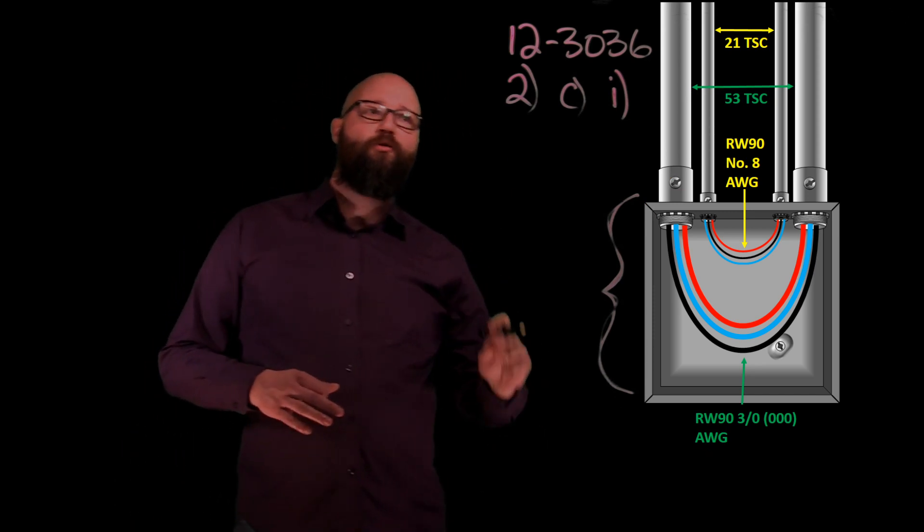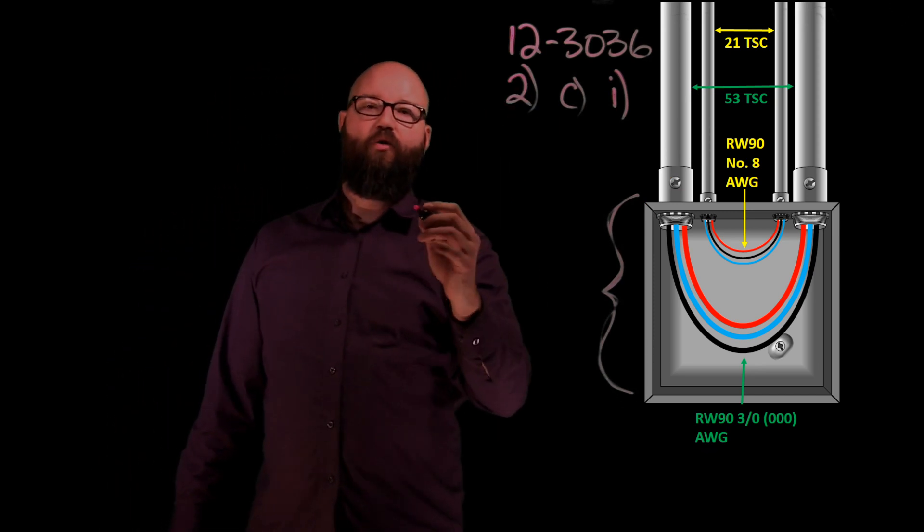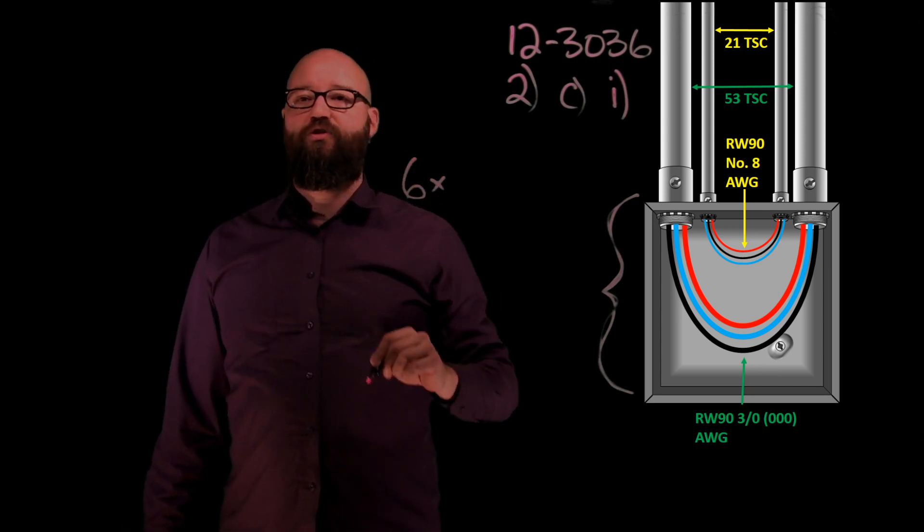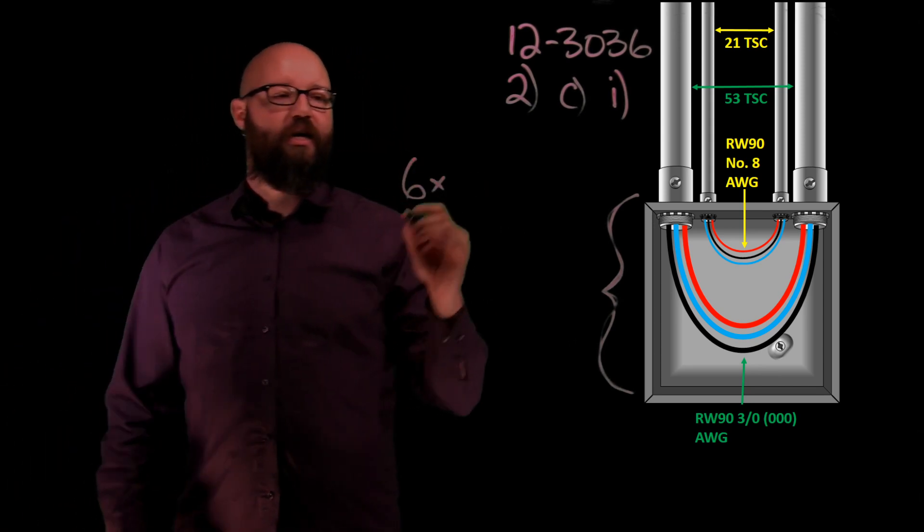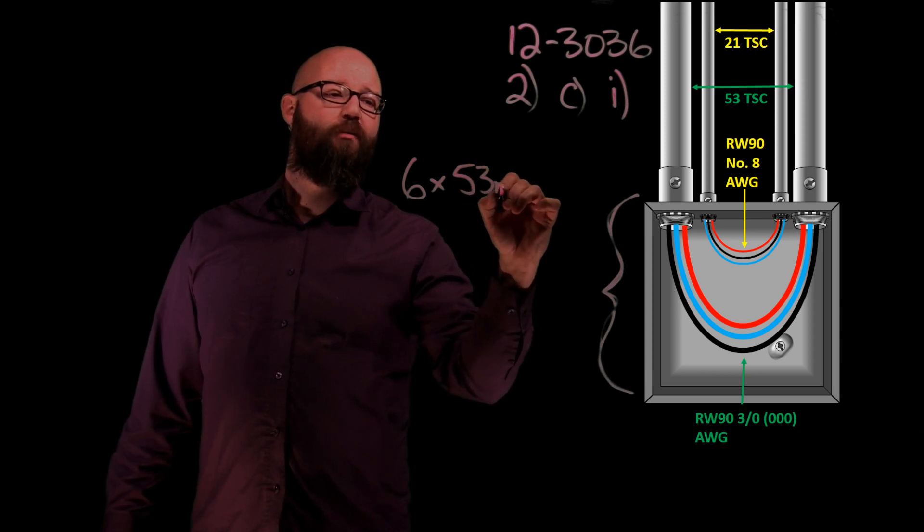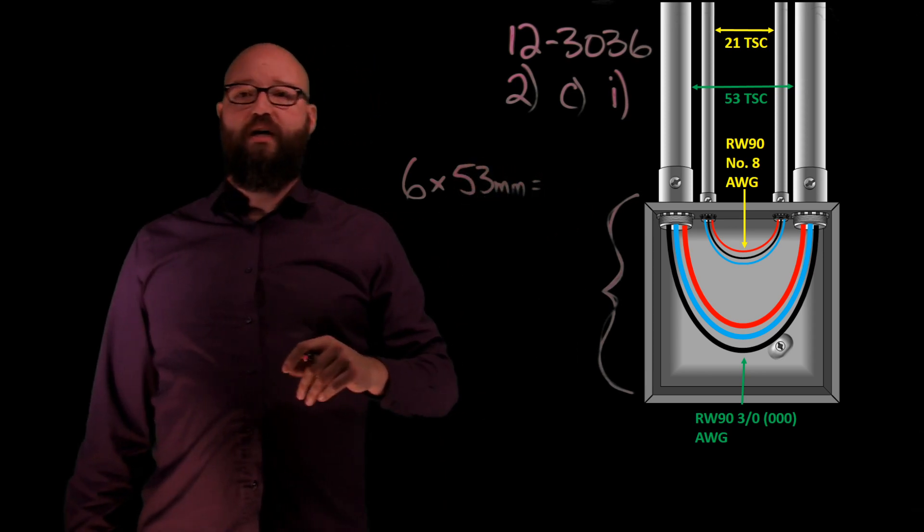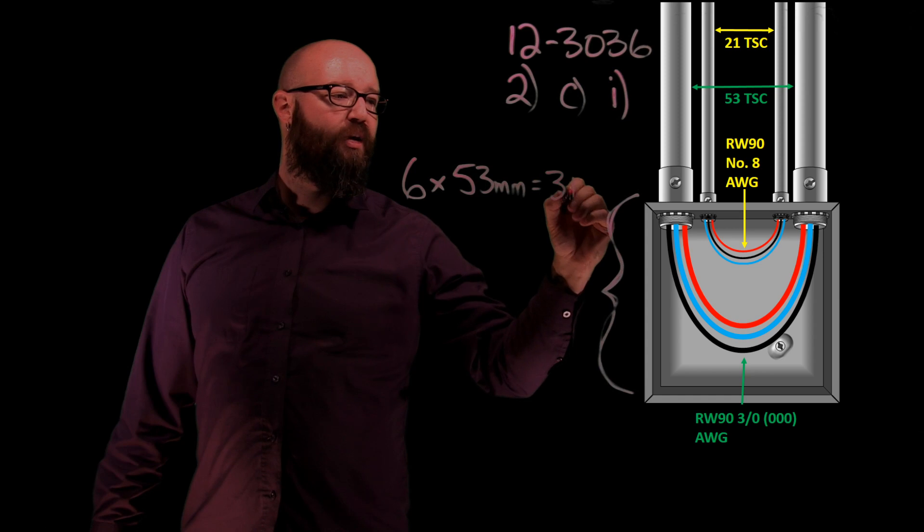So if you remember, 12-30-36 tells me that we are going to take six times the largest trade size diameter, which in this case is 53 millimeters, which gives us a measurement of 318.